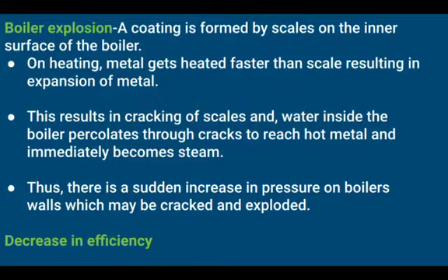And when a metal is heated, it will slightly expand. So as the metal expands, the scale that is present inside will not expand, and this results in the cracking of scales, and water inside the boiler will percolate through cracks to reach the hot metal and immediately it becomes steam.